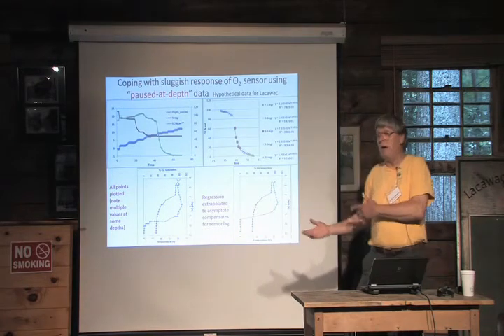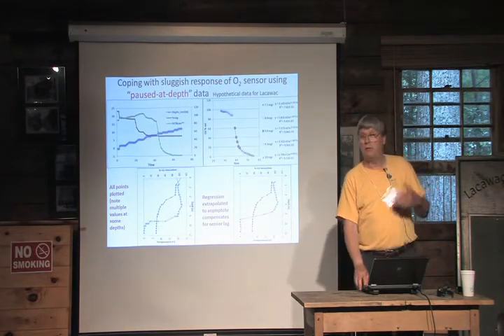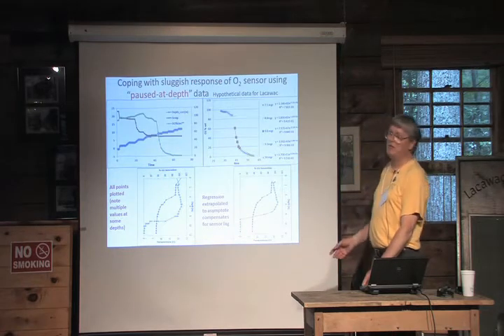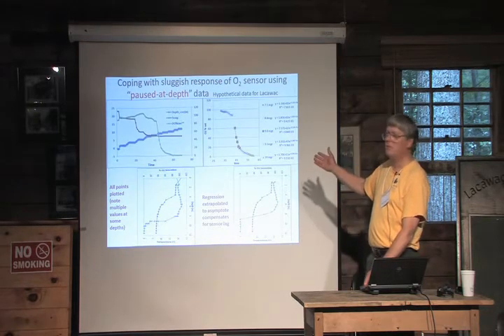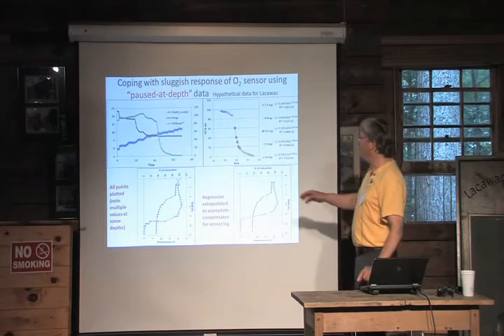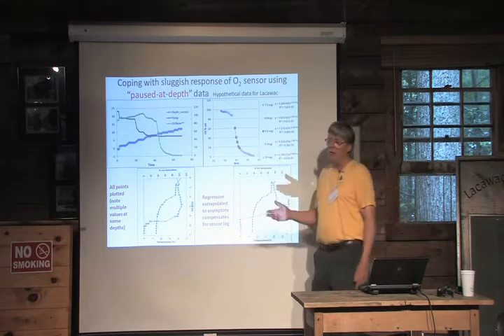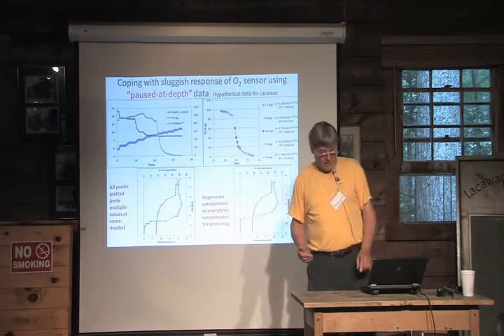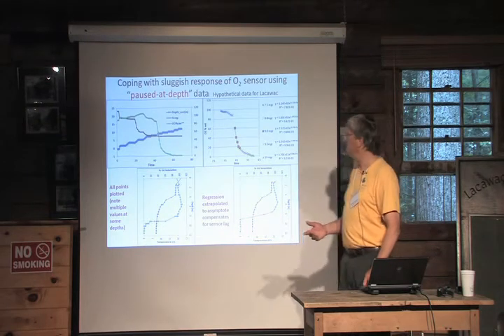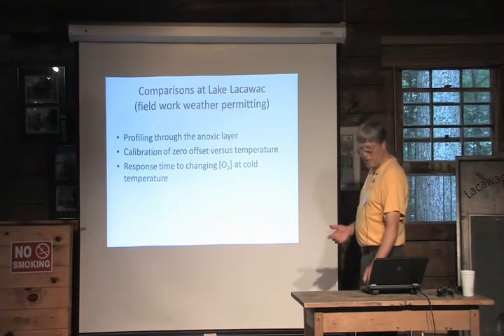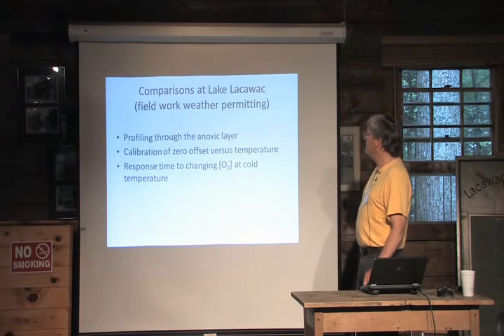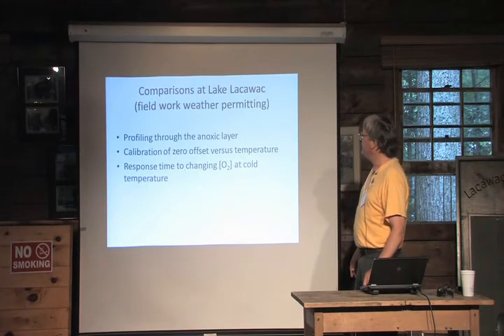The point is it would be even better to use a fast oxygen sensor, but if you don't have one, and most of the oxygen sensors that we use are too slow to do this very well, it's extremely valuable to collect more than one point. And it applies equally well to pH data, any other sensor that responds slowly, even oxygen.